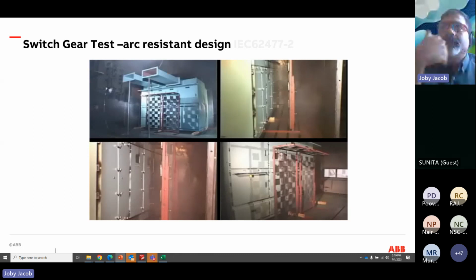So whenever an arc flash occurs, the heat propagates out and expands, and the exit is through that trapezoidal tunnel, and it will go somewhere else actually. And there are also other kinds of protection we normally use, related to arc flash detecting sensors, so that whenever an internal flash or an arc occurs, it senses it and immediately trips the circuit. So there are various methodologies we have adopted when it comes to arc flash mitigation.